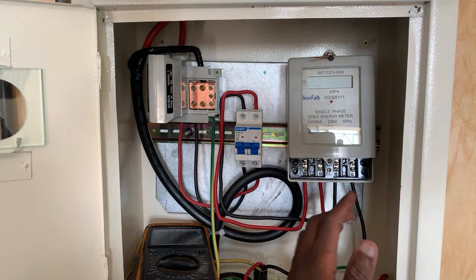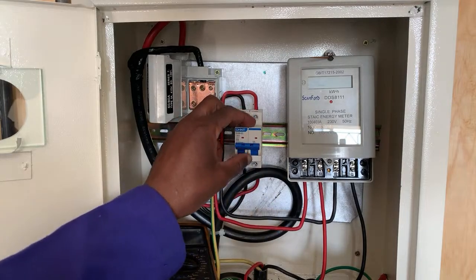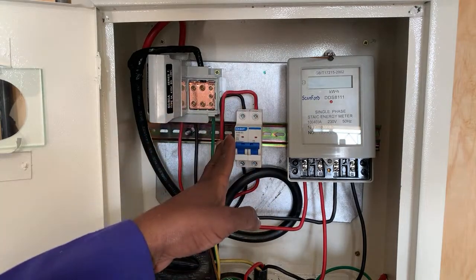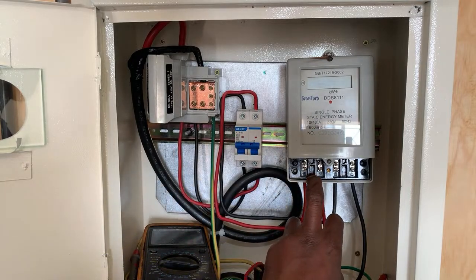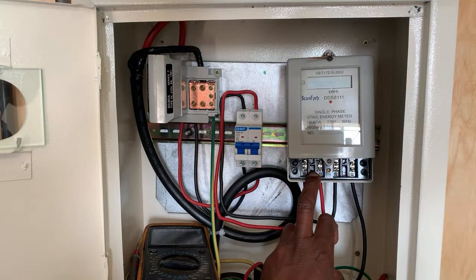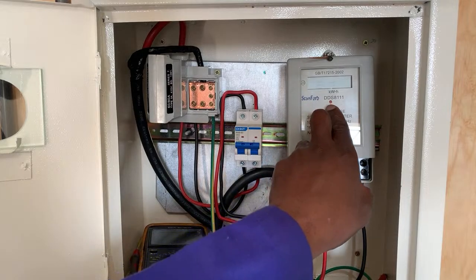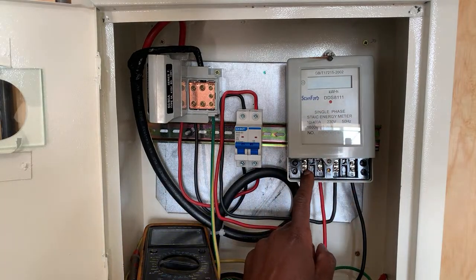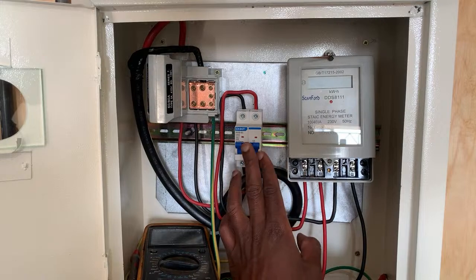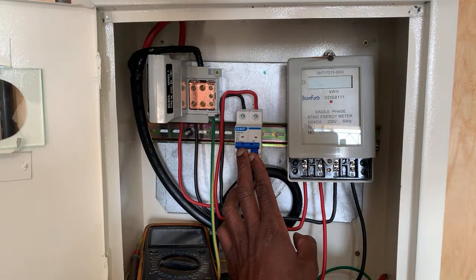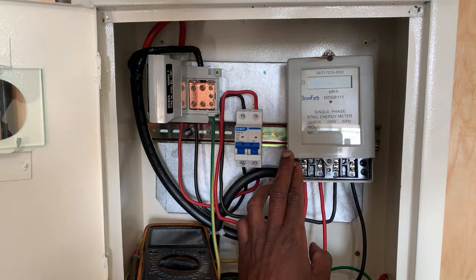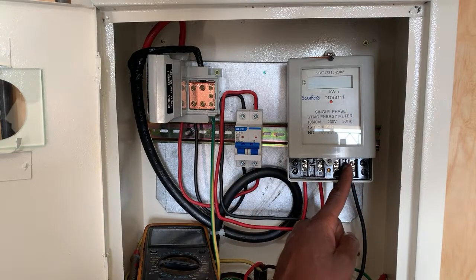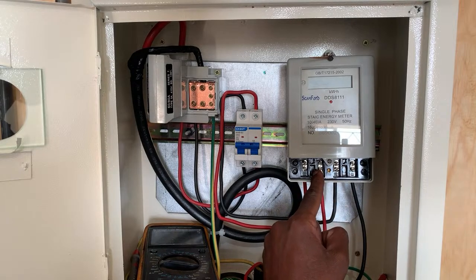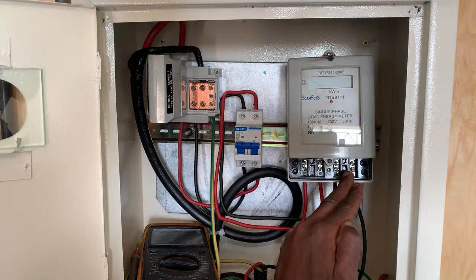All right. Now, assuming that this double pole is well connected and there is an output, but at this energy meter there is an issue, where it's not indicating any flow of electricity through this diode here, then it will mean that there is also a loose connection at this particular point where we have the input from this double pole switch. In most cases it is hard to find such a fault, but the fault is normally on the output of the energy meter, because the load is drawing current from the meter.